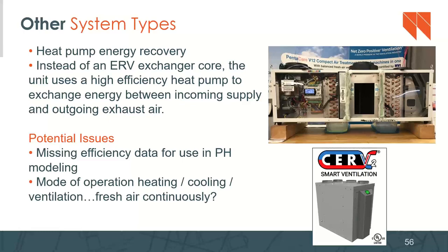In both the Minotaur and the CERV, it is actually heat pump energy recovery. So within these systems, as we understand it, there is no core. It is not an energy recovery thing that's going on here. And this next bullet is taken right from CERV's website: Instead of an ERV or exchanger core, the unit uses a high efficiency heat pump to exchange energy between incoming supply and outgoing exhaust air. So the incoming and outgoing exhaust air here is the ventilation air, but you're using some of the waste heat of the heat pump process in order to make this happen. But it's important to note that it's not a straight up ERV. You're not approaching those efficiencies.